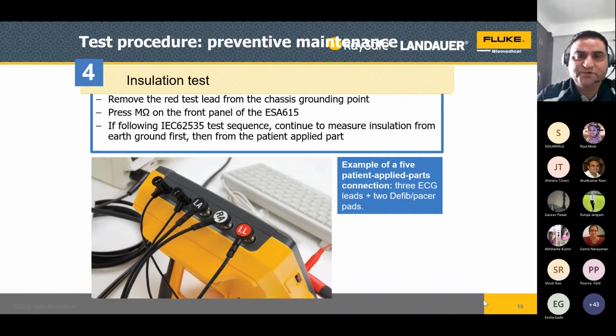Basically, if it is above 2 mega ohms, your equipment insulation is very good. Suppose it is measuring 10 mega ohms, basically your equipment is okay. But it should not go below 2 mega ohms. If it is below 2 mega ohms, then your equipment fails. If one parameter fails out of 10 parameters, still your equipment fails. You cannot use that particular equipment on a patient. Please remember this.